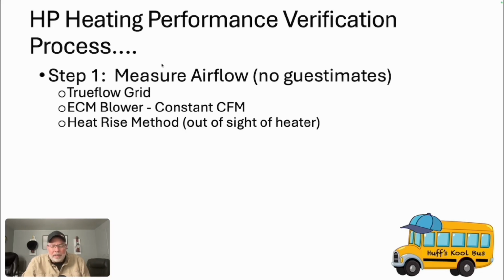The heat rise method, and this is specifically when you have an air handler with a strip heater. You can do heat rise method on a gas furnace, but it's not near as accurate because we would have to know the actual firing rate and then the net BTUs to be able to use that information. Whereas with the heat rise method, when you have an air handler with a strip heater, you're able to measure the voltage and the amp draw at the heater, and then also the temperature rise across that heater. And we can use that information to be able to determine airflow.